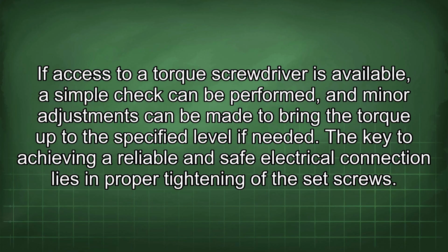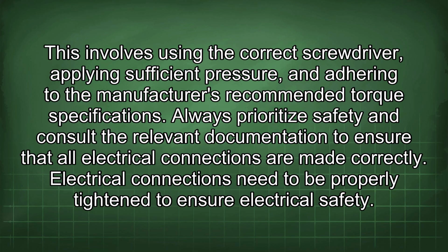The key to achieving a reliable and safe electrical connection lies in proper tightening of the set screws. This involves using the correct screwdriver, applying sufficient pressure, and adhering to the manufacturer's recommended torque specifications. Always prioritize safety and consult the relevant documentation to ensure that all electrical connections are made correctly. Electrical connections need to be properly tightened to ensure electrical safety.